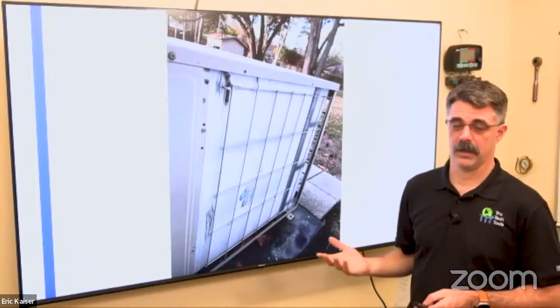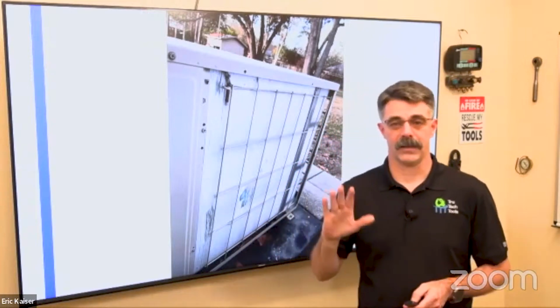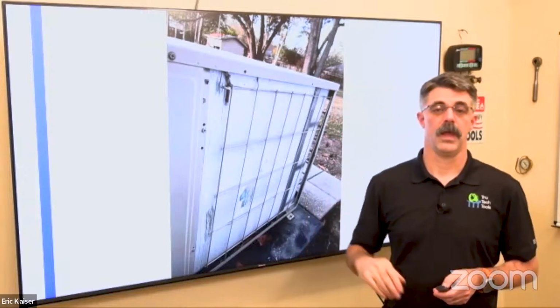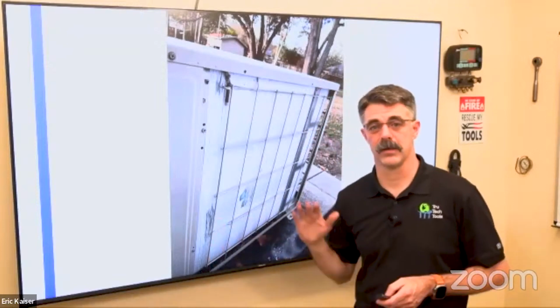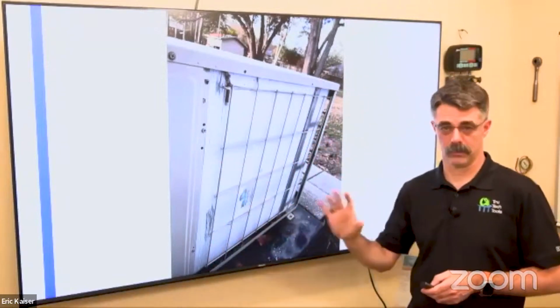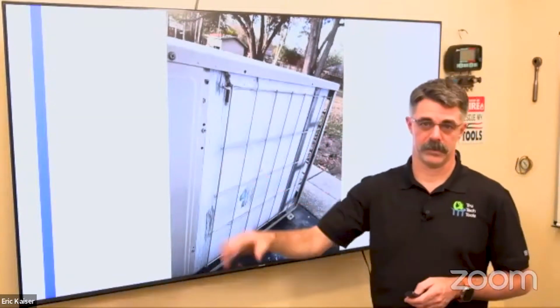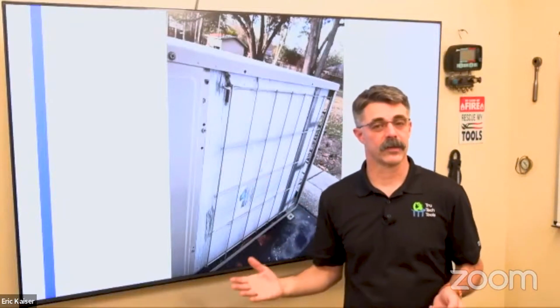I have gotten a lot of calls over the years when I was working for contractors. "Yes, sir. Can you come out right now? That new heat pump you put in, yes, it's on fire." No, your heat pump's not on fire. That's a defrost cycle. And the customer understanding that was on us as the contractor because we didn't properly explain it. So make sure we're properly explaining that your customer understands. It's going to run in the wintertime. It's going to make a puff of steam when it comes out of defrost. And that's perfectly normal.